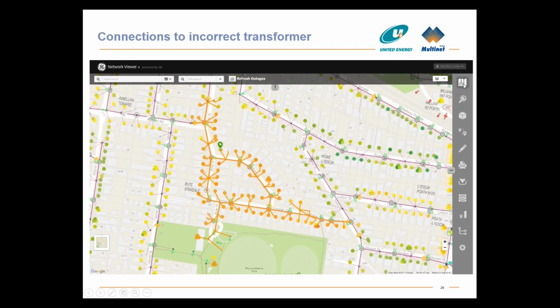Some of the other nice features we've deployed, which look good alongside the high voltage one, is if we turn on our cross-referencing layer. This is something that tells us where analytics ran across the network and identified places where we think customers are most likely not on this transformer, or adjacent customers are actually on this transformer. So we see there's an open point, and another open point, so those customers are all very close to open points. We quite frequently see that customers are connected to the wrong side of an open point. Analytics now helps us confirm that.